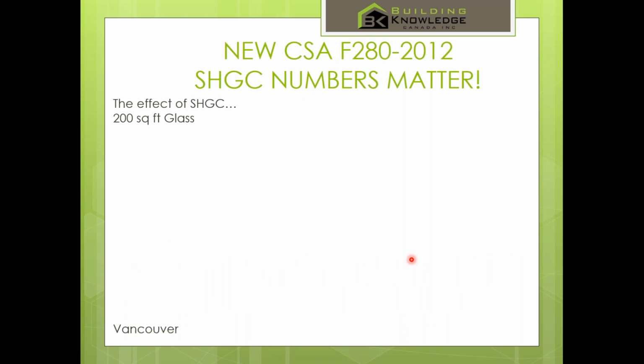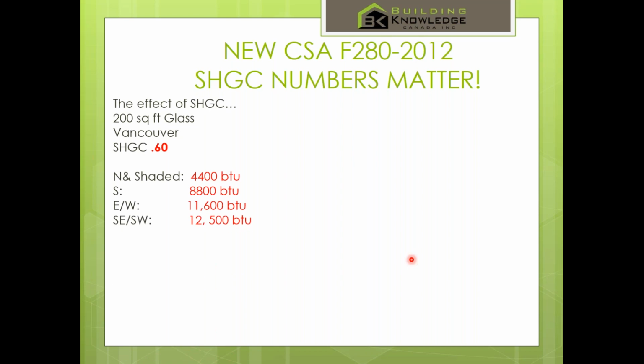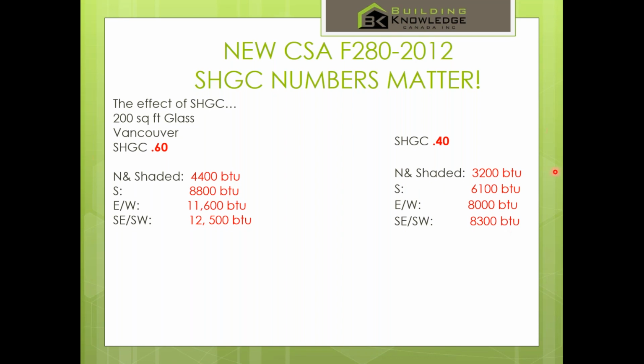and I'll just show you how. On a typical house, you've got 200 square feet of glass. I'm going to put you in Vancouver at a solar heat gain of 0.6. We have seen glass with that high of a solar heat gain. That means that you're looking at tonnage for glass on that side. You're looking at almost a full ton of cooling just for that kind of glass on the south side, southeast, southwest side of the building. If you simply change your solar heat gain, for literally no cost for most window manufacturers, all of a sudden you're going to start to see the size of your tonnage change from 12,000 down to 8 and less on other sides, and that's by simply going with just a standard 0.4 solar heat gain, which still falls on the high side.